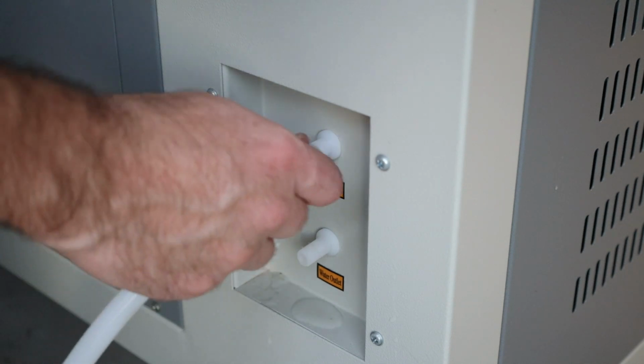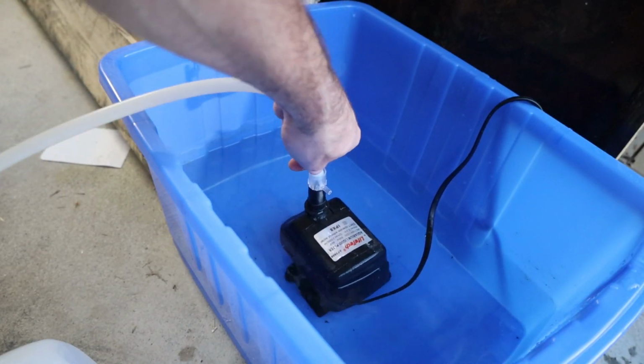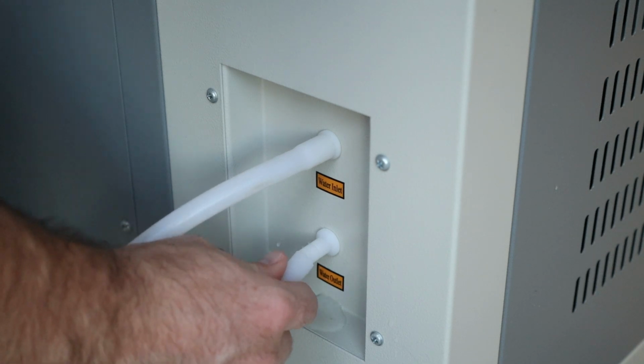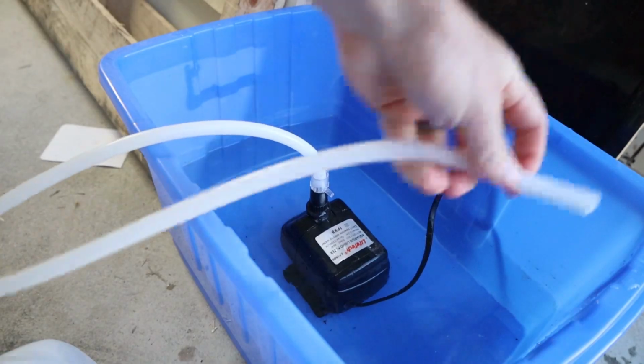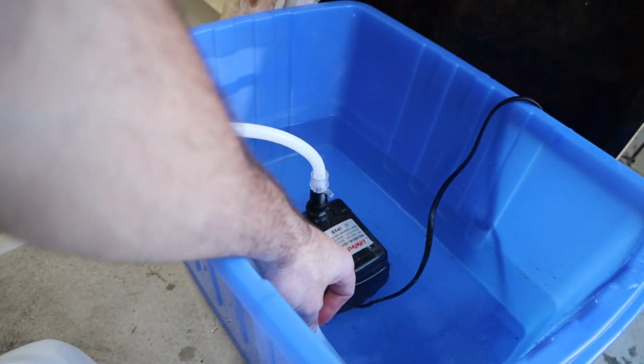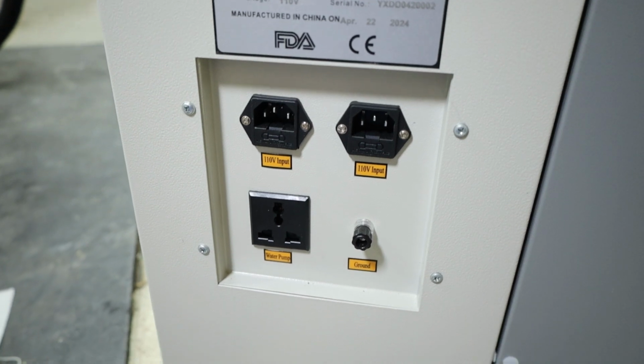One of the provided tubes connects to the inlet port of the laser and the top of the pump, while the other tube connects to the outlet port of the laser and goes back into the tote. Then the pump itself gets suction cupped to the bottom of the tote and plugged into the outlet on the back of the laser.